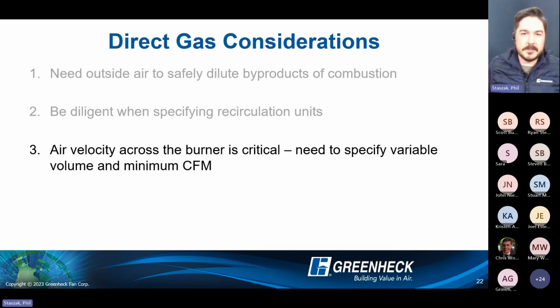Another conversation piece with direct gas fired is variable volume. A lot of times now when we talk about general makeup air, you don't always need to move 10,000 CFM. That's your worst case design. If you can move the exhaust down as well as the supply, overall operating costs drop significantly. A kitchen is a great example. You order a unit at say 5,000 CFM for a large kitchen application, and we allow up to 50% reduction in the same box on a direct gas fired unit.